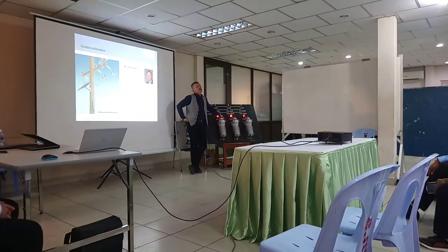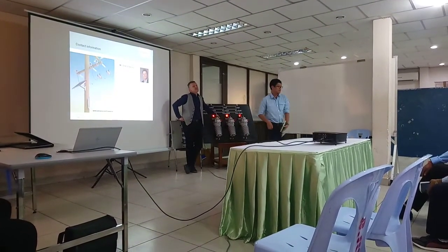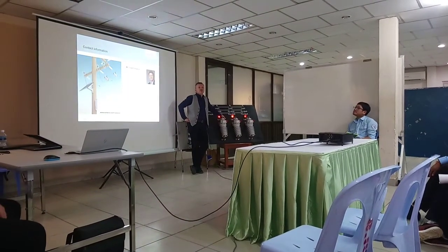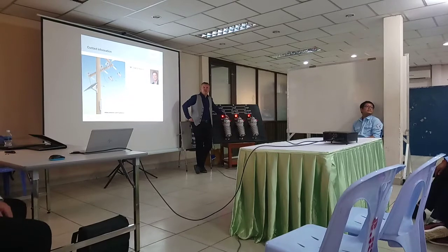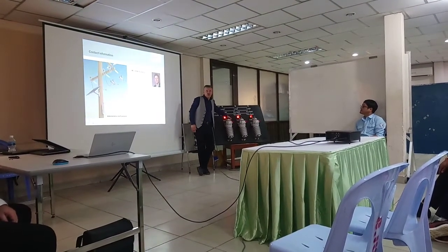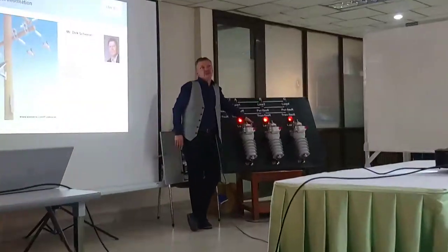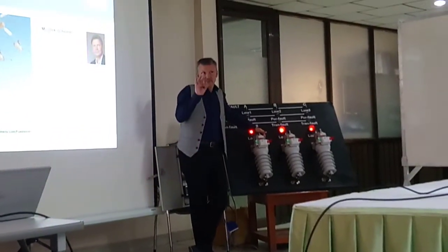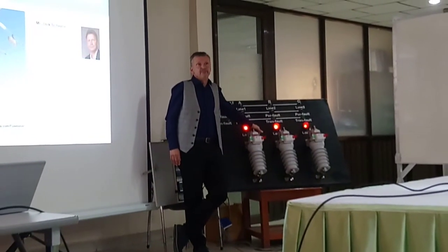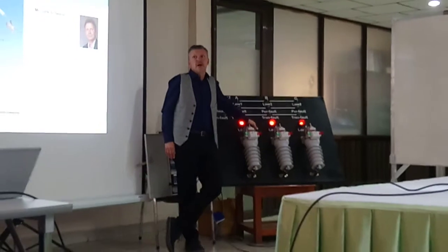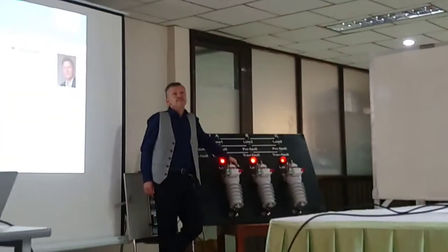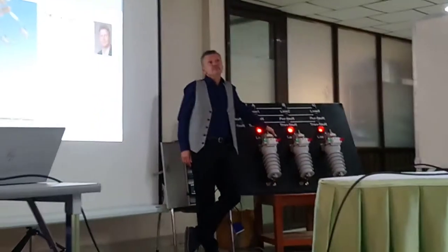How many seconds of trip when the bird touches the line? How many seconds to trip again? To close again? The dead time is between 2 and 10 seconds, or more than 10 seconds. For the three-phase device, if you have operated again, 10 seconds. It's a minimum time. Up to 30 seconds. 30 second maximum.